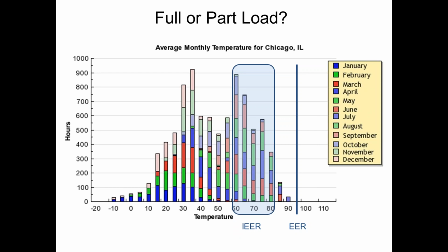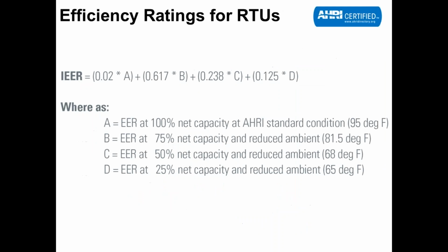There is a newer metric called IEER, Integrated Energy Efficiency Ratio. This is the part load efficiency of mechanical systems such as rooftop units and split systems. And this tests the efficiency when it's not a peak scenario. So this is more appropriate for what we care about here, where we're trying to figure out, well, how many hours are we running at 65, 70, 80, 85 degrees. That's more interesting to me than a 95-degree test point.